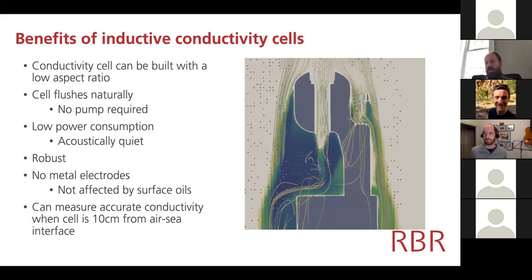If you make a conductivity cell with electrodes in it, these typically are high aspect ratio. That is to say, they look like a straw. They might be tens of centimeters long, but only a few millimeters in diameter. And as you know, if you pushed a straw down through the water column, no water is going to want to pass through the middle of the straw. It's all going to flow around the outside. So therefore, when you have an electrode-based cell, and particularly for profiling applications, but even for moored, a pump is typically required. And the pump causes you two problems.